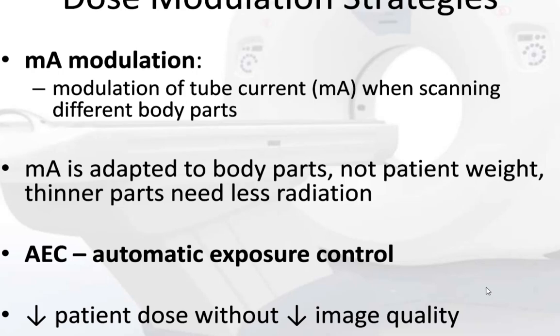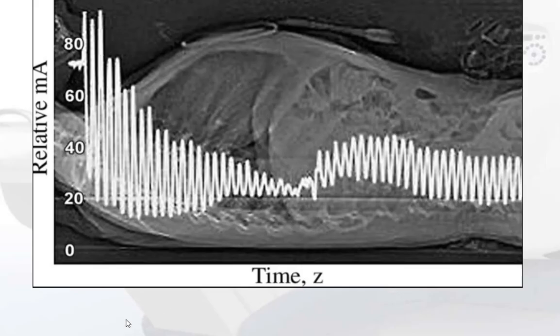There are other dose modulation strategies. MA modulation is the modulation of tube current when scanning different body parts — MA is adapted to the body part, not patient weight. Thinner parts need less radiation. AEC is automatic exposure control.